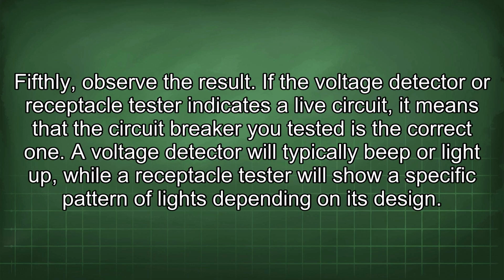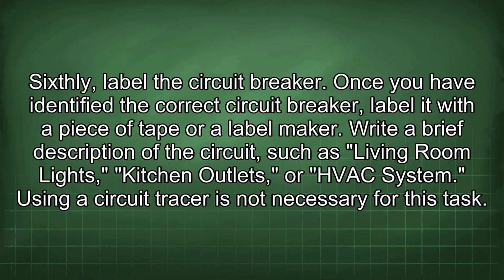Fifthly, observe the result. If the voltage detector or receptacle tester indicates a live circuit, it means that the circuit breaker you tested is the correct one. A voltage detector will typically beep or light up, while a receptacle tester will show a specific pattern of lights depending on its design. Sixthly, label the circuit breaker. Once you have identified the correct circuit breaker, label it with a piece of tape or a label maker. Write a brief description of the circuit, such as living room lights, kitchen outlets, or HVAC system.